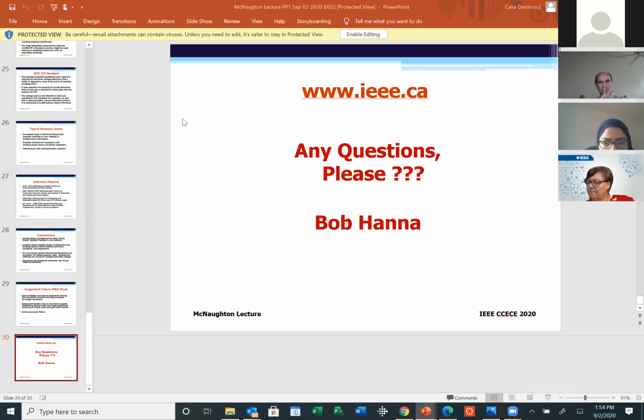Well, is there any work done to manufacture these chargers with harmonic suppressors that do not feed back any harmonics into the system, albeit it might be more expensive units? Well, again, excellent question. I doubt it, because at the end of the day, these guys sell chargers for a specific dollar value. The moment you try to introduce harmonic correction, then you add to the value. And to be honest with you, we're talking about chargers of 5, 6, 7, 8 kilowatts. So everybody is saying, well, it's not my problem.